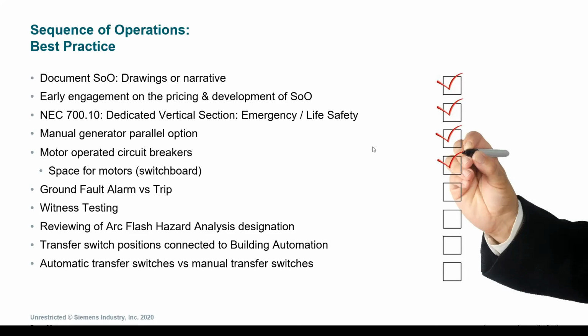Transfer switches come in different sizes and different types. Two of the types I want to specifically mention is the automatic transfer switch versus the manual transfer switch. The automatic transfer switch, as described, automatically performs the task of going between normal, emergency source, and back to normal. A manual transfer switch requires actual manual operation from a qualified individual to change the position of the transfer switch. Depending on the time or the duration of the outage, if resources don't allow, this could force an extended outage for certain systems that are already connected via the manual transfer switch to the generators, delaying or extending that outage and impact.